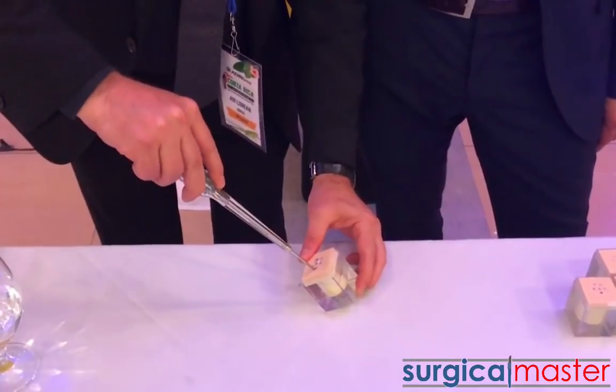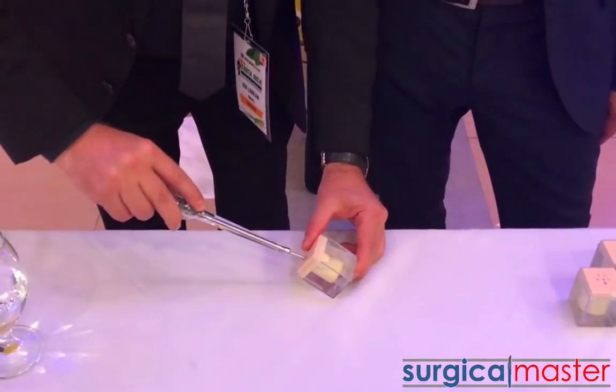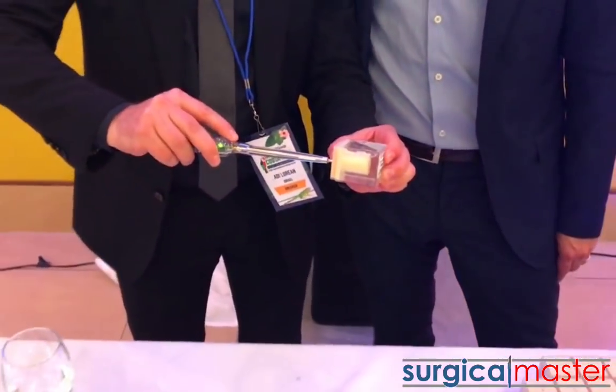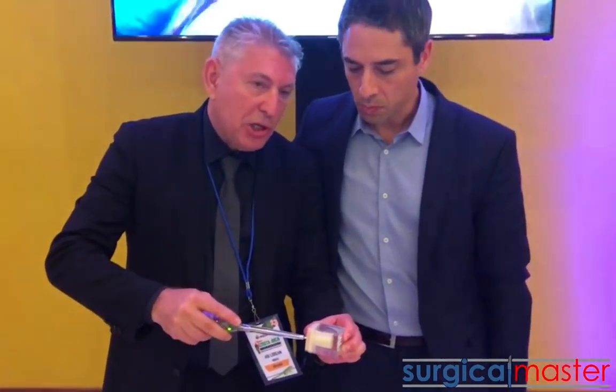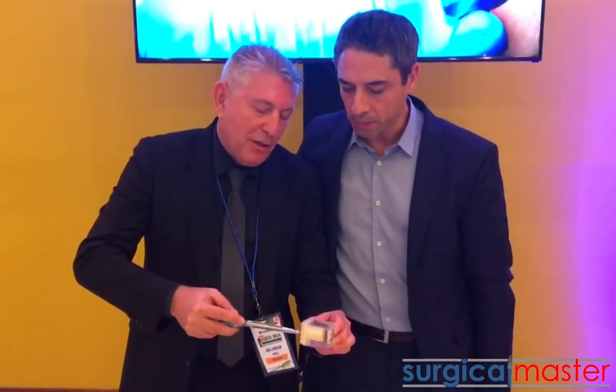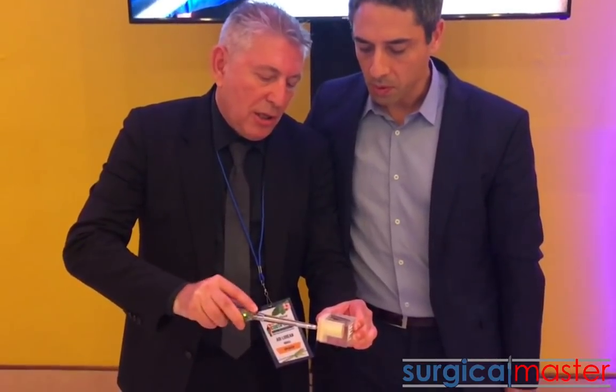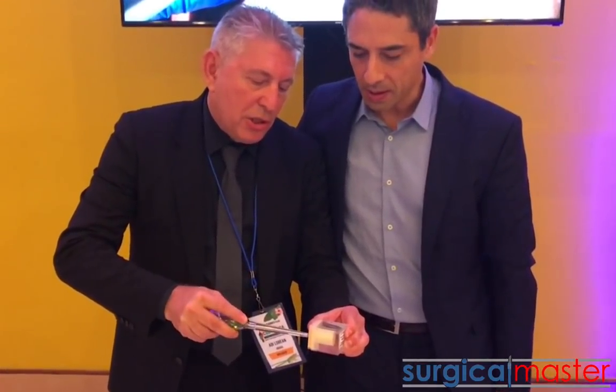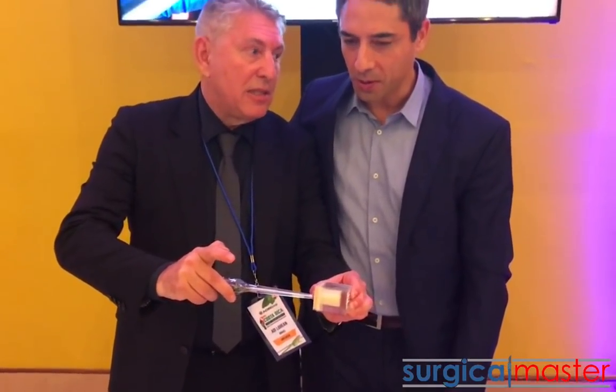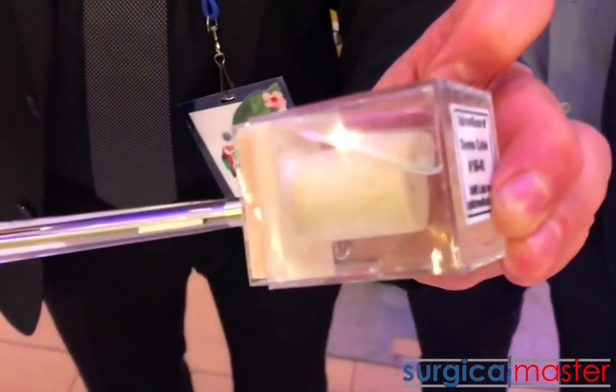Now let's go all the way through this bone model from orthopedic surgery — a huge chunk of bone. In cortical bone, as you can hear, there is no sound at all. But pay attention — now I'm breaching what would be the sinus membrane. You can hear the sound change. That's the alert. It's a real-time alert. It's almost there but not there — 0.3mm away. This is the signal for the surgeon: stop, we've reached the place. If you keep breaching, you can hear the alert increasing.